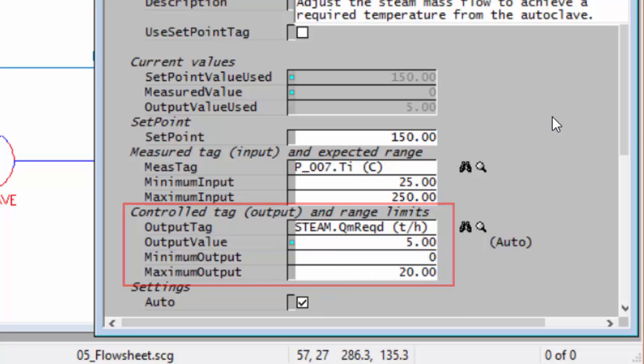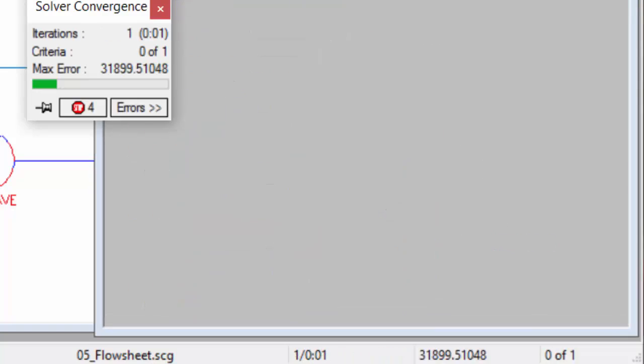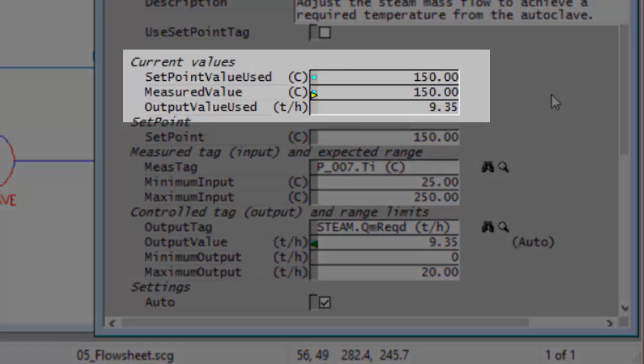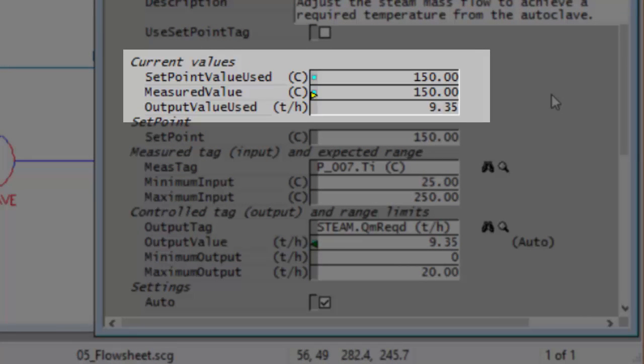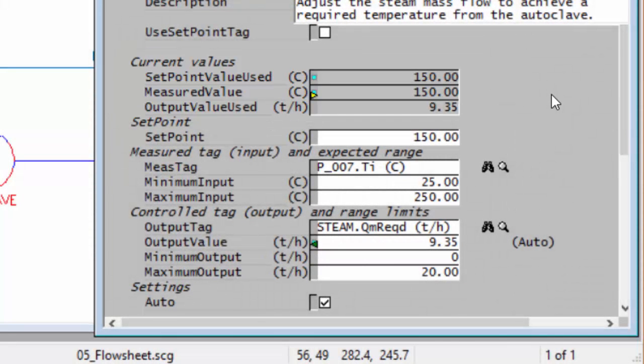PID is now all set up and it's ready to do its control. We've told it we want P_007 to get to 150 degrees and go and adjust the amount of steam. So I'll push the run button and you can see it's pushed in 9.35 tons an hour of steam to achieve 150 degrees from the autoclave.